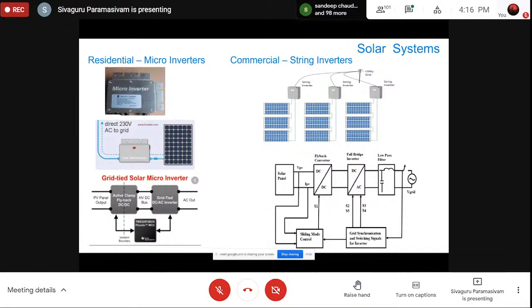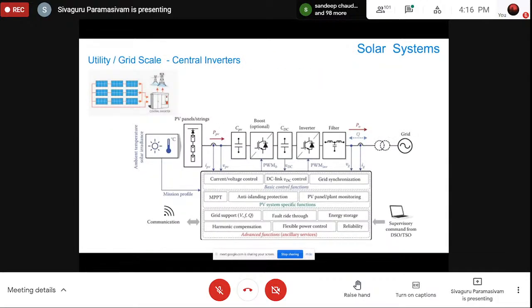This is the second type of solar system. And the third type of solar system is called grid scale or utility scale solar systems, and the type of inverters that we use there are central inverters. The minimum central inverter capacity available today in the market is 1000 kilowatt, which is 1 megawatt, and the maximum size that we have today is 3.5 megawatts. You can imagine that one unit is about 3 meters long, 800 mm in depth, and about 2 meters in height. That box will give a power of 3 megawatts. When connected to the solar panels, it can inject 3 megawatts of power continuously to the grid as per the irradiation levels. And that's a huge chunk of power electronics again.